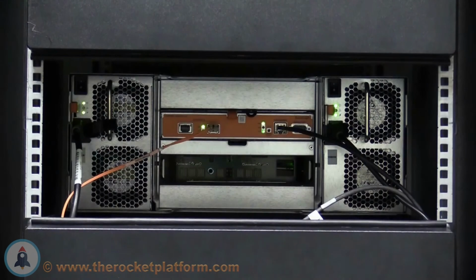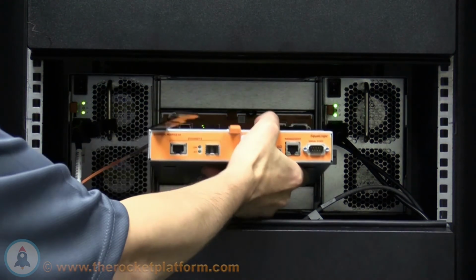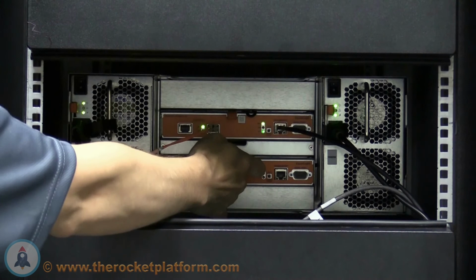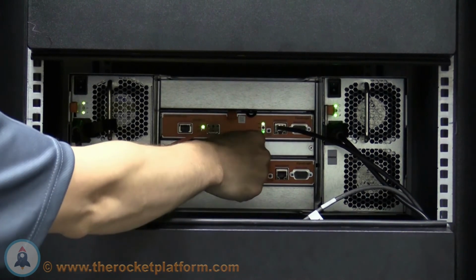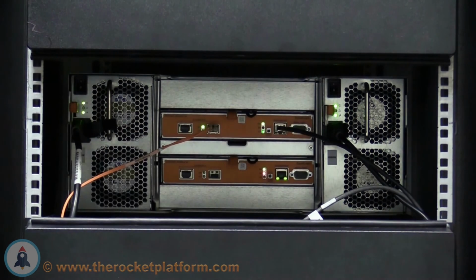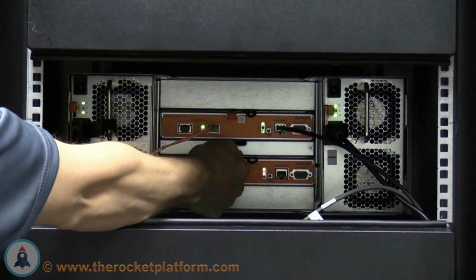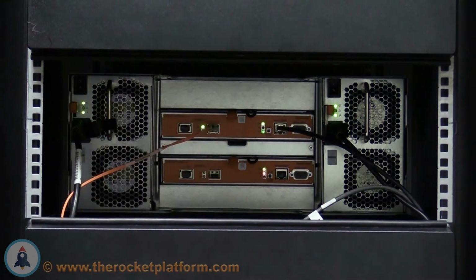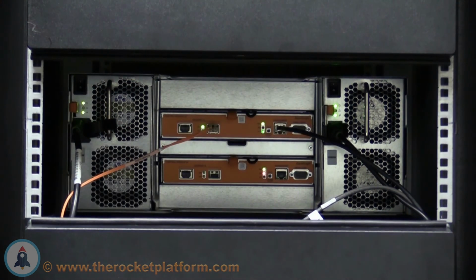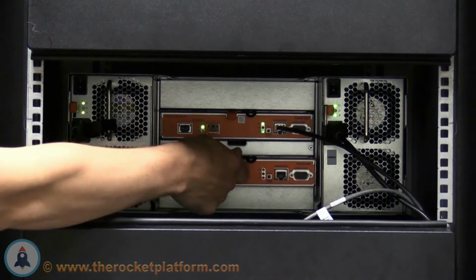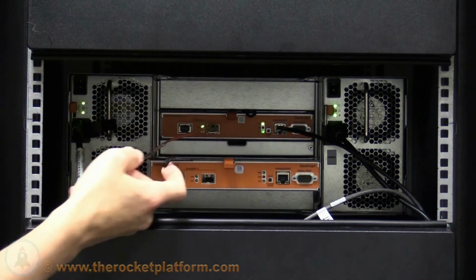Open the lever all the way on the replacement controller, then insert it into the slot. Once the controller is seated in around 90%, the lever on the control module will begin to catch. Once the lever begins to catch, push the lever inwards until you see or hear the orange tab click into place. Attempt to pull the controller backwards without releasing the locking mechanism. If the controller stays in its slot, then it is seated properly. If the controller moves around in the slot, you must reseat the controller.